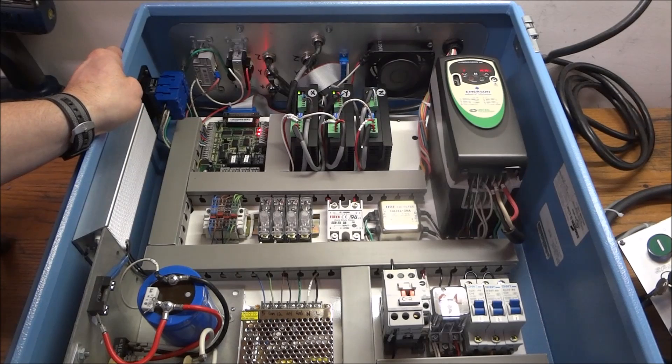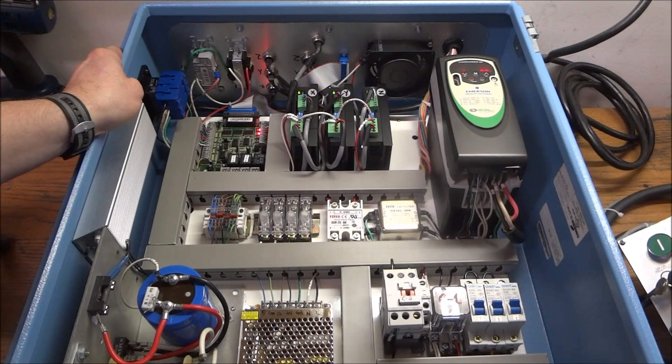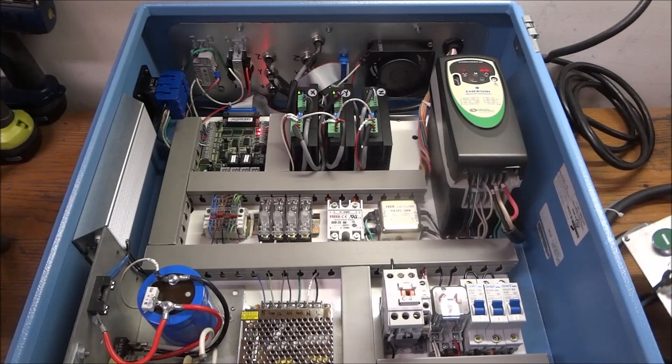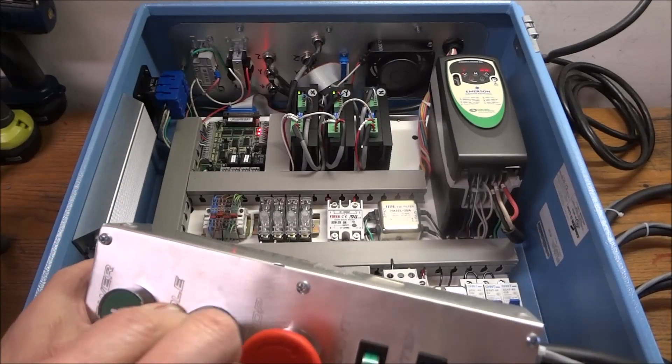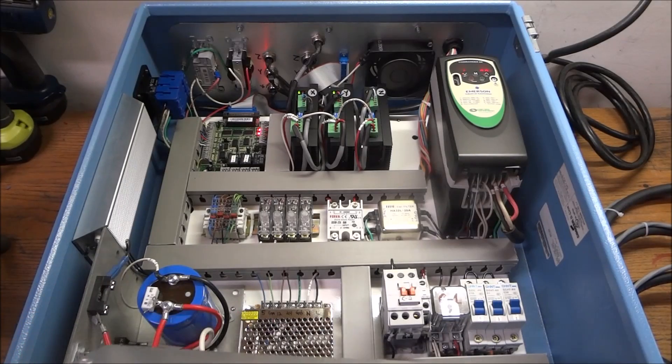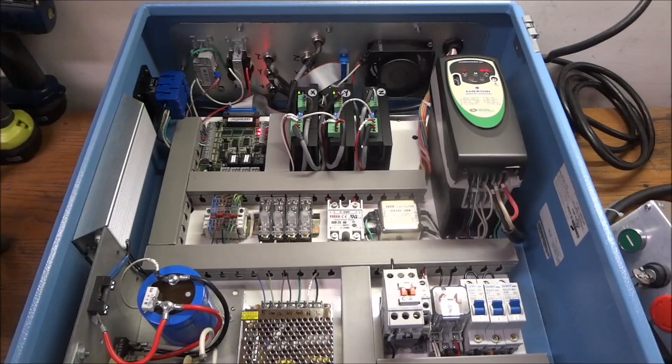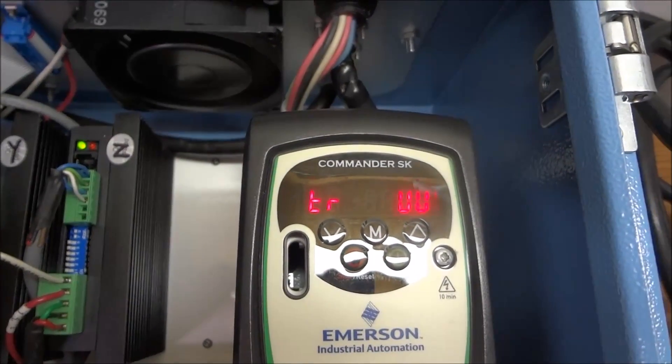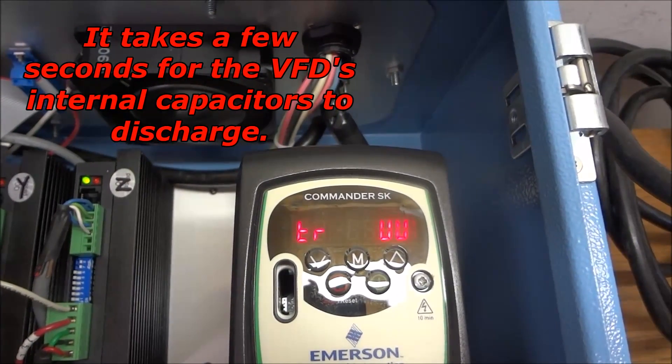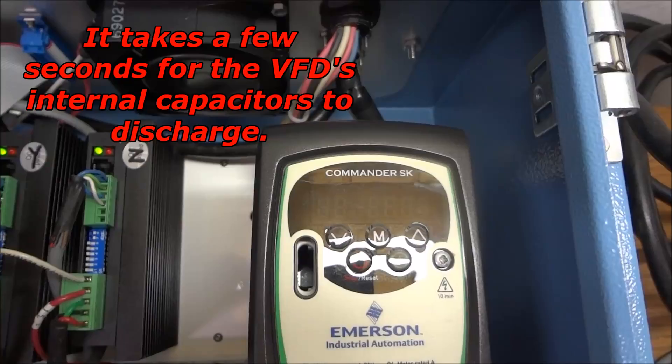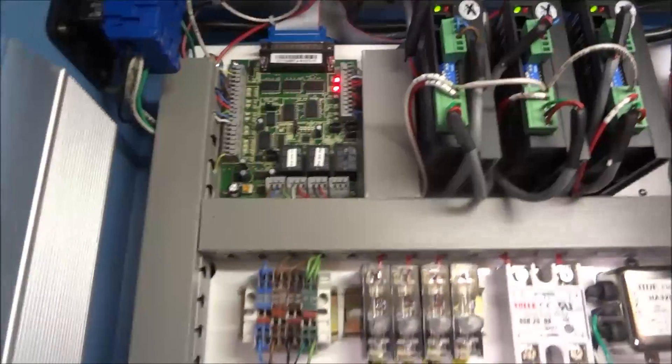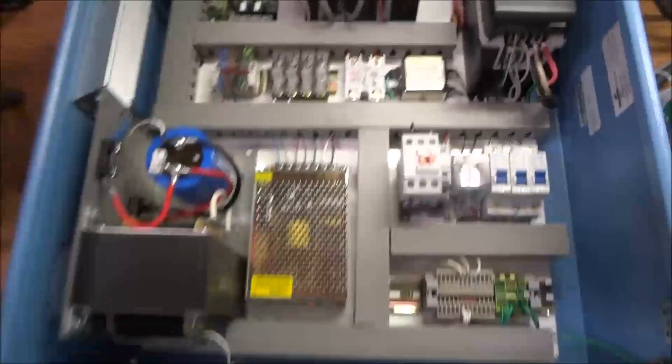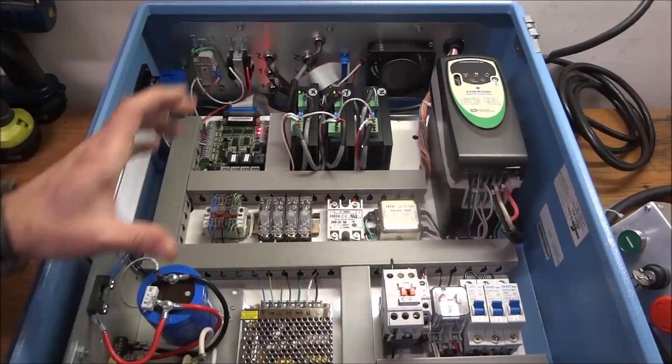So I don't see any blue smoke. Everything looks good. I'm pretty satisfied with the overall panel. And if I disable the spindle, our C2 contactor pulls out. As you can see, it's sticking up now. And our power on our VFD dies. It has capacitors in there, so it takes a minute for it to drain. But you can see that we've lost power. But everything else is still up and running. And so if we want to use our touch probe to indicate our part, we can do so.